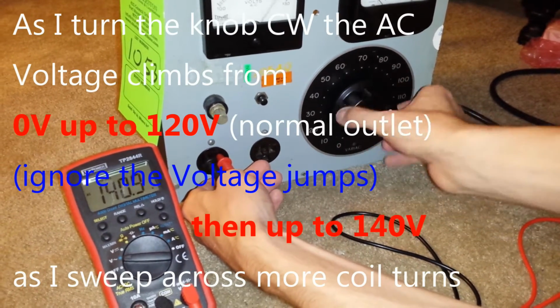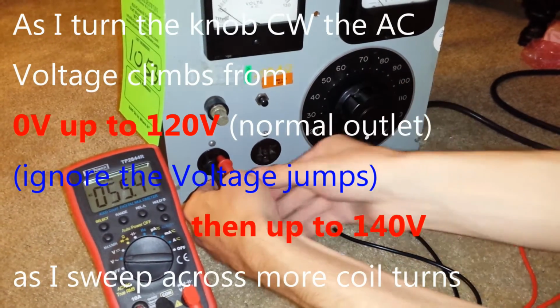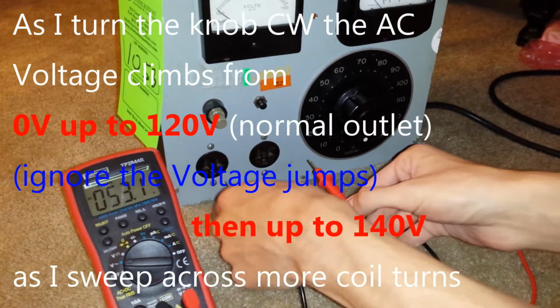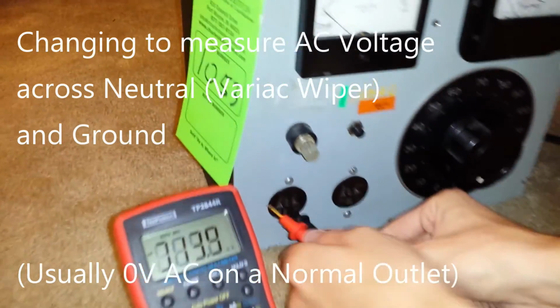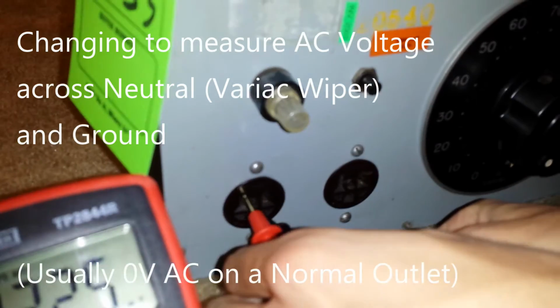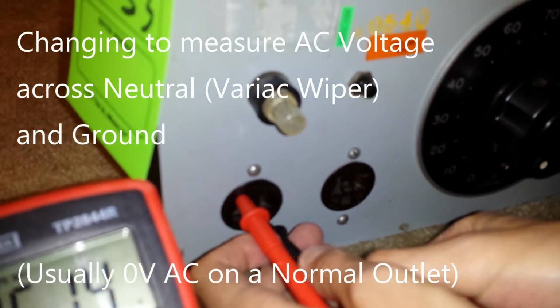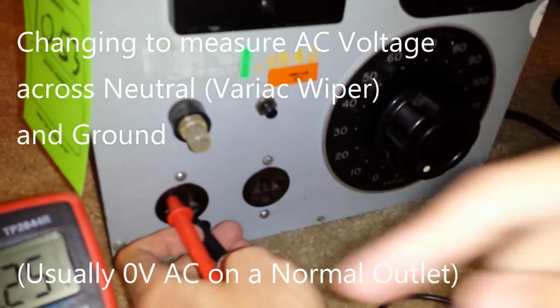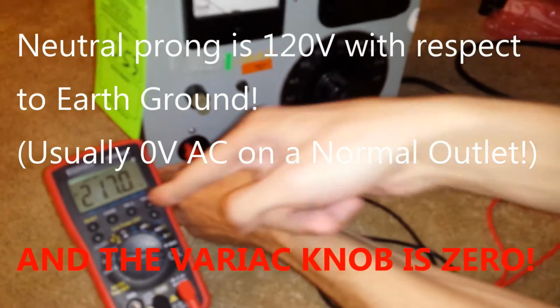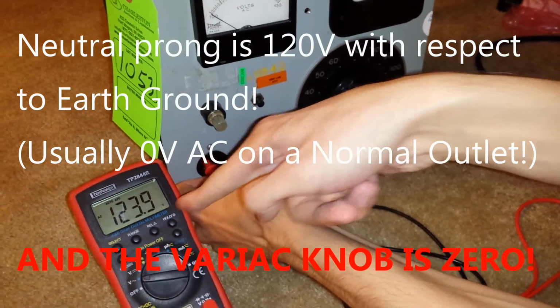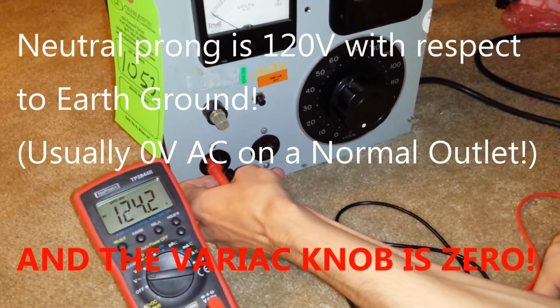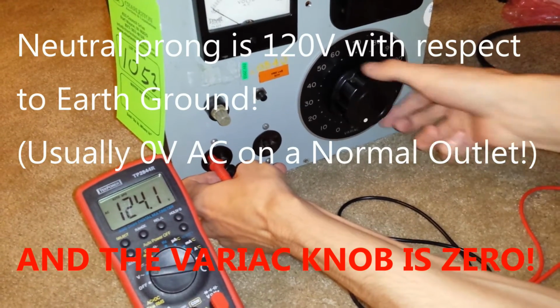Now I'm changing to measure the AC voltage across the neutral, which is still the Variac wiper, and earth ground. And normally this measurement comes up as about 0 volts on a normal wall outlet. You can see that the neutral prong, which is connected to the wiper, is actually 120 volts with respect to earth ground. And that's with the Variac knob set to 0.